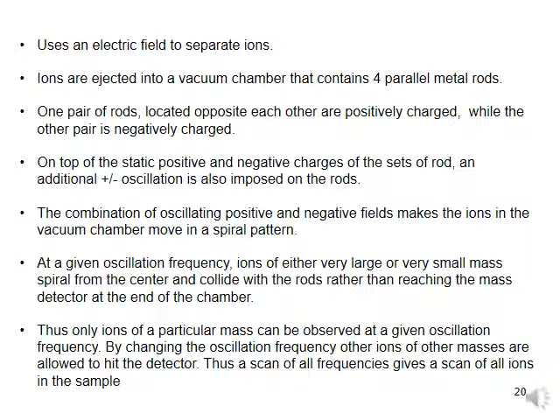This text explains the process of how the ions accelerate in between the rods. Thus only ions of a particular mass can be observed at a given oscillation frequency. So we determine the frequency, and then we can see the signal that comes to the detector based on different frequency. By changing the oscillation frequency, ions of other masses are allowed to hit the detector. Thus, a scan of all frequencies gives a scan of all ions in the sample. So you can get all the ions that are ionized in your sample. This method is very good.